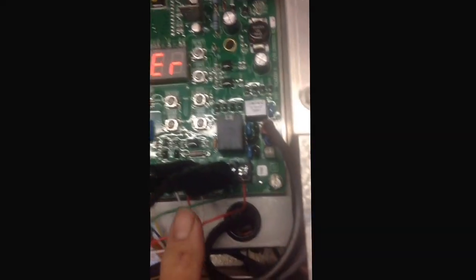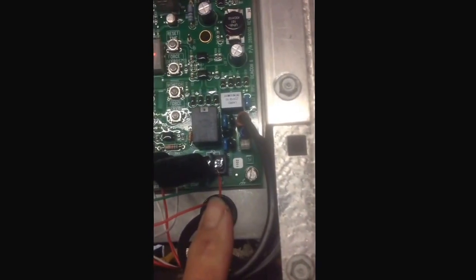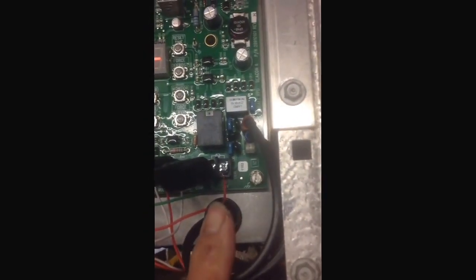We have a service display down there — it says 'SER' on that display all the way down there. We also take the compressor wire off of compressor and move it to the 24-volt terminal, which will keep the compressor on, because you need some time for it to draw down or keep drawing down. This took a couple minutes to do.